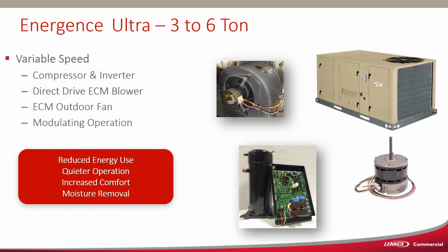So on the 3 through 6 ton, it has a true inverter compressor, variable speed compressor, an ECM2 variable speed direct drive blower motor, and an ECM variable speed condenser fan motor. So the Prodigy board is going to control all of these components the way it feels fit, using its algorithms in order to produce the most energy efficient, quietest, and increased comfort and moisture removal, to optimize all of those things.